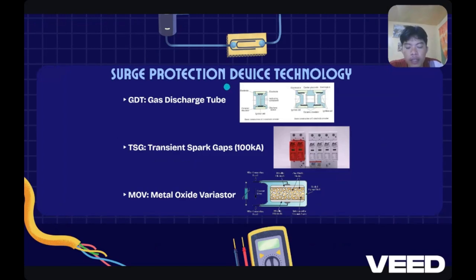Surge protection device technology. First is gas discharge tube or GDT. Gas discharge tubes are a specific type of lightning or surge arrestor. These are commonly used to protect sensitive electronic and telecommunication equipment from high voltage transients like lightning strikes.